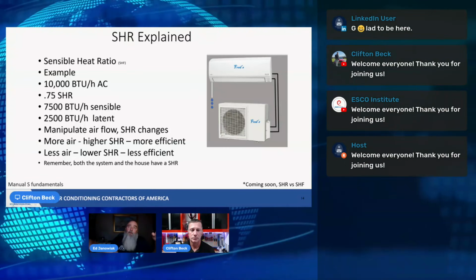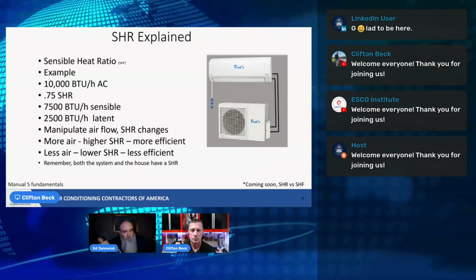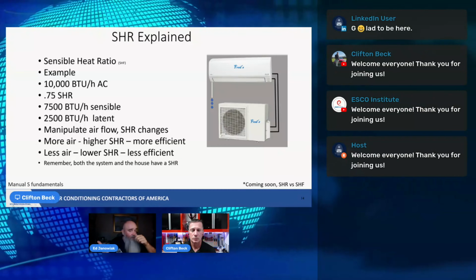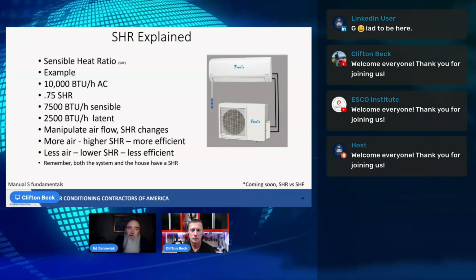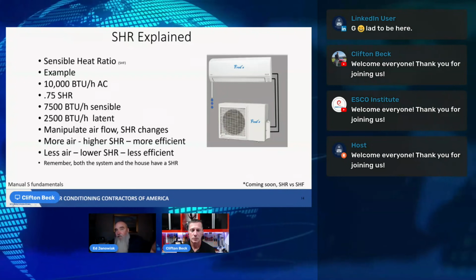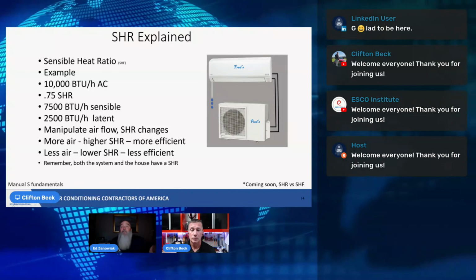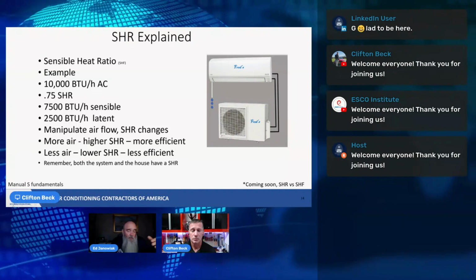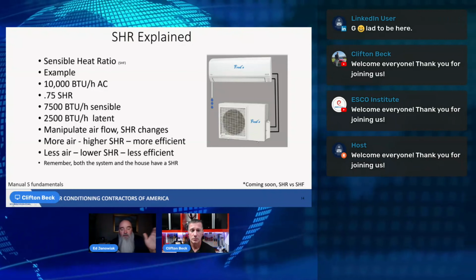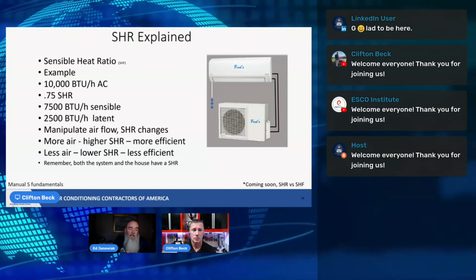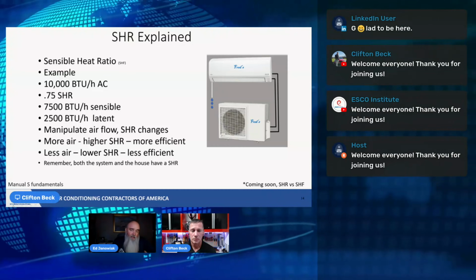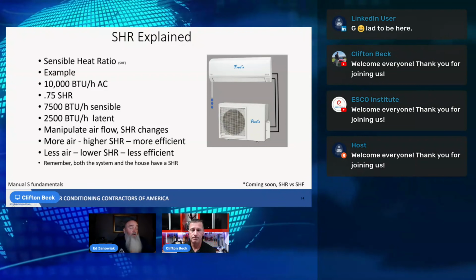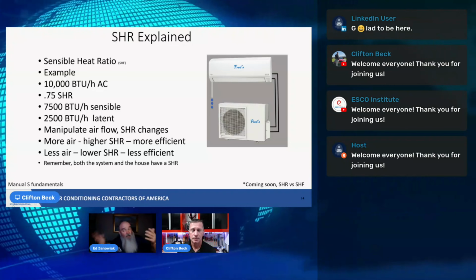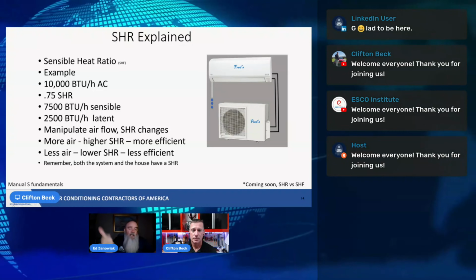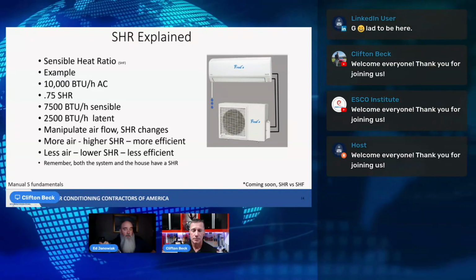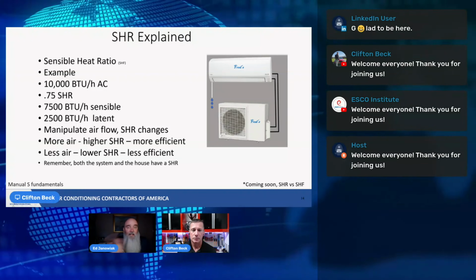What happens with the equipment when we run higher airflow, more total capacity, more sensible capacity, we see sensible heat ratios that can eclipse 0.8, maybe even higher. The flip side, less airflow, we're going to see that sensible heat ratio decrease. We're going to see a lower sensible capacity, a lower total capacity. We're going to see an increase in latent capacity, which can be beneficial. High sensible heat ratio, more efficient. Low sensible heat ratio, less efficient.